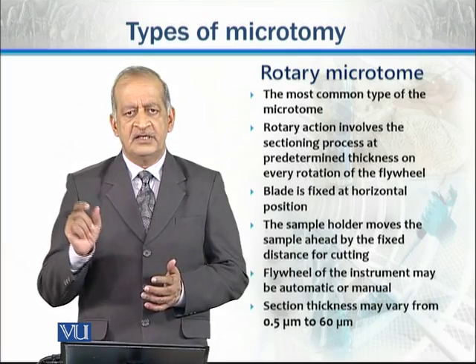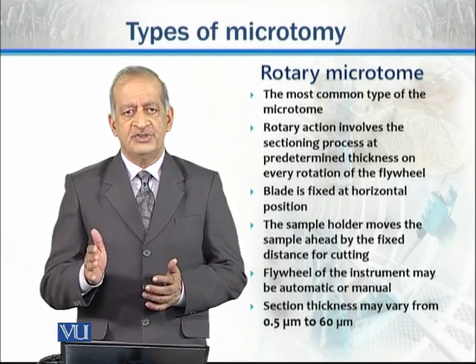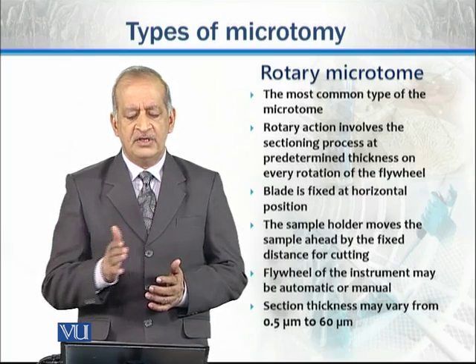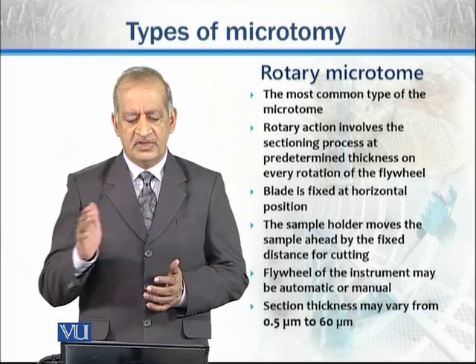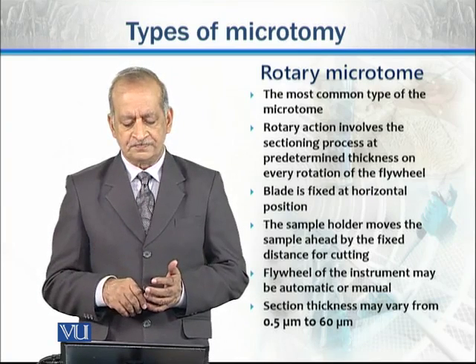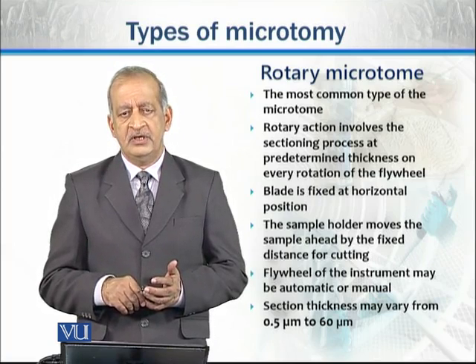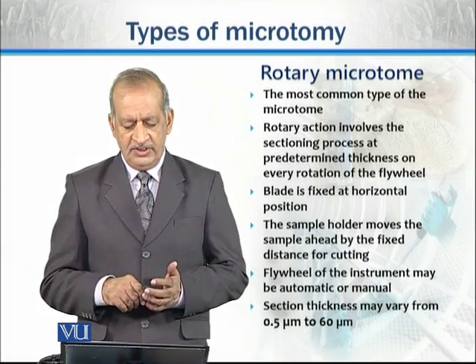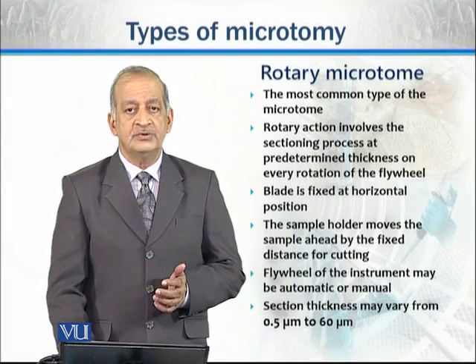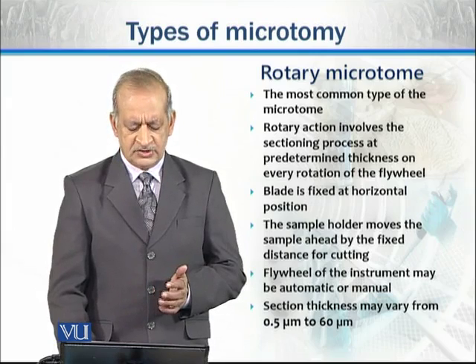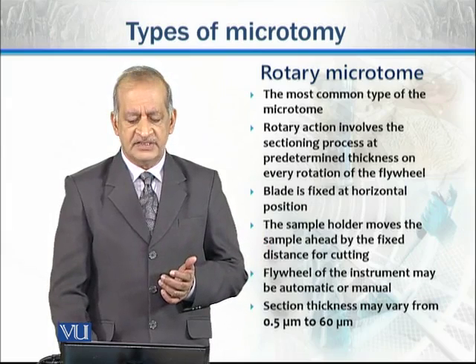For example, if we fix the section thickness at 10 micrometers, the sample holder will advance the sample by 10 micrometers after every rotation. The flywheel may be automatic or manually operated, and the section thickness can vary from 0.5 micrometers to 60 micrometers, depending on whether thin or thick sections are required.